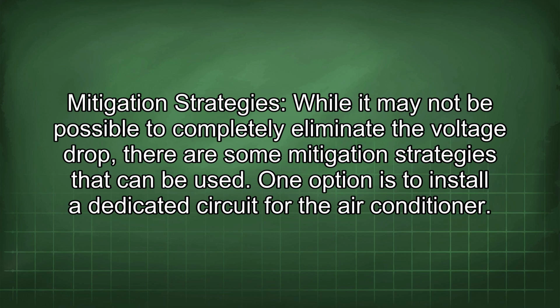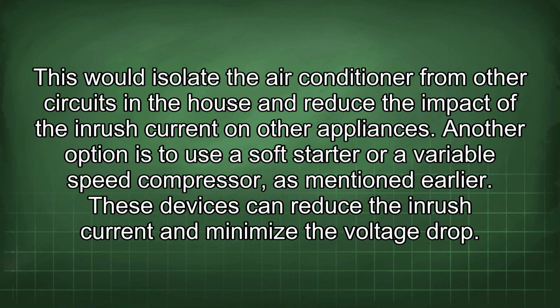Mitigation strategies. While it may not be possible to completely eliminate the voltage drop, there are some mitigation strategies that can be used. One option is to install a dedicated circuit for the air conditioner. This would isolate the air conditioner from other circuits in the house and reduce the impact of the inrush current on other appliances. Another option is to use a soft starter or a variable speed compressor, as mentioned earlier. These devices can reduce the inrush current and minimize the voltage drop.